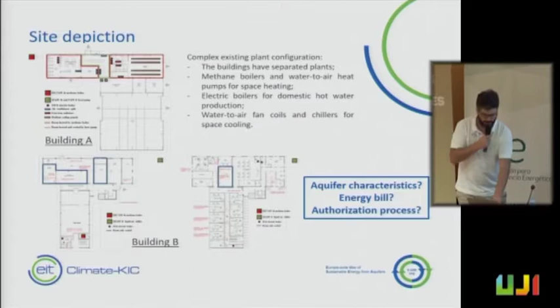There was a complex system of plant that originates from a sort of stratification. So year by year they just add some further plants to produce heat or cool - a quite common situation. So we have methane boilers or water-to-air heat pumps for space heating, electric boilers for domestic hot water production, and also water-to-air fan coils and chillers for space cooling.